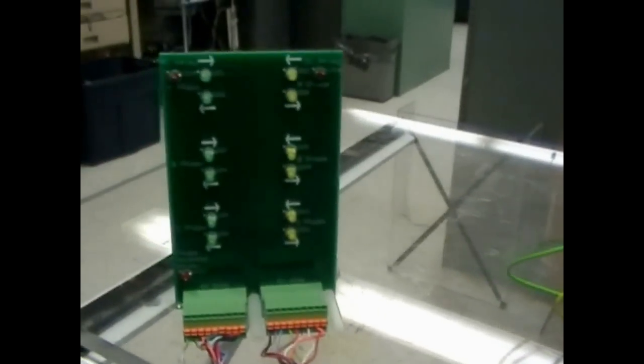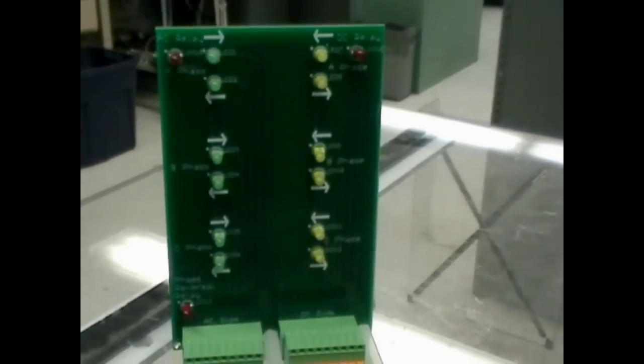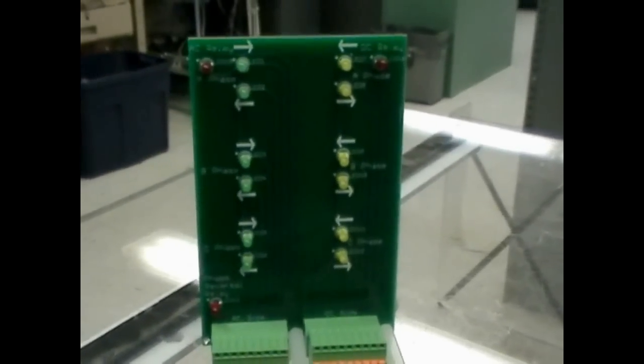This is the annunciator panel. So it has 12 LEDs, as you can see, the main ones, the green on the left and the yellow on the right. So when the stator of the DFM is connected to the DC source, the 6 LEDs on this side, the yellow ones, turn on. Each indicates the thyristors which I showed earlier. And when the stator is connected to the AC source, the green LEDs turn on. There are additionally 3 more LEDs, the red ones, which indicates whether the phase of the AC source is reversed, and this is required for full negative speed operation. And the other 2 LEDs are mainly contactors for protection.